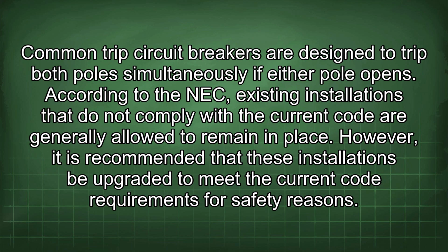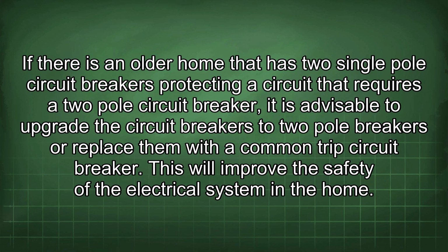According to the NEC, existing installations that do not comply with the current code are generally allowed to remain in place. However, it is recommended that these installations be upgraded to meet the current code requirements for safety reasons. If there is an older home that has two single-pole circuit breakers protecting a circuit that requires a two-pole circuit breaker, it is advisable to upgrade the circuit breakers to two-pole breakers or replace them with a common trip circuit breaker. This will improve the safety of the electrical system in the home.